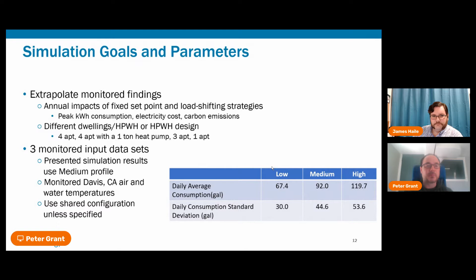This slide looks at the electricity cost and peak period electricity consumption with those 4 different system designs that I talked about previously. And you can see that when we switch from each apartment having their own heat pump water heater to the shared configuration with 4 apartments sharing an 80-gallon heat pump water heater, the annual electricity cost drops substantially. And this is because of jacket losses. Now you have 1 heat pump water heater instead of 4, so there's less jacket losses and simply less load. But it doesn't perform as well in terms of load shifting performance, and there is more electricity consumption during the peak period when using the shared configuration.